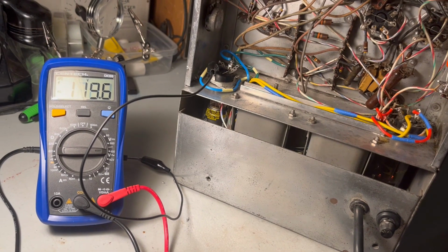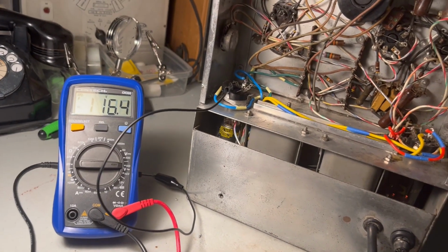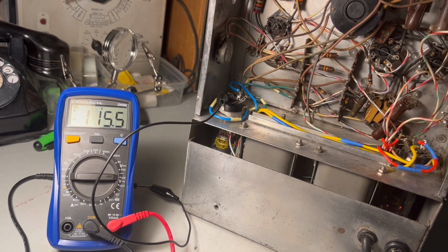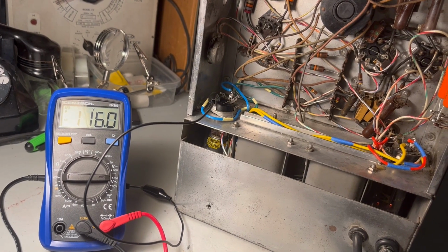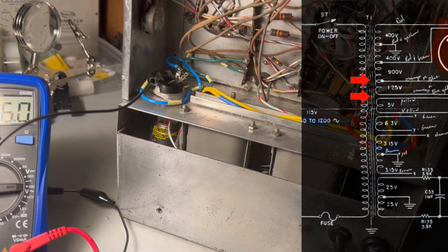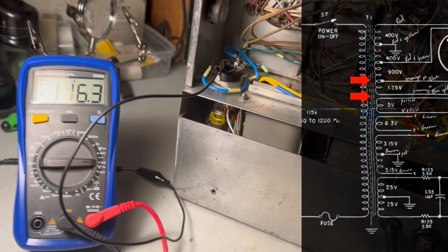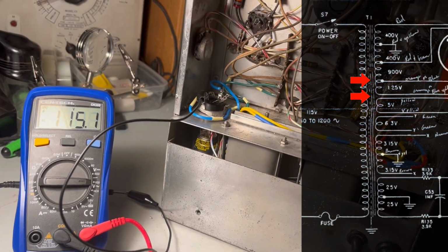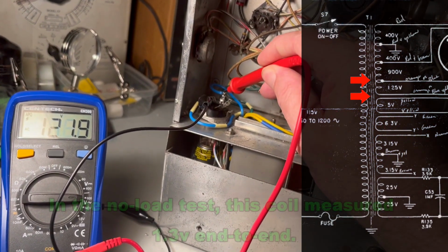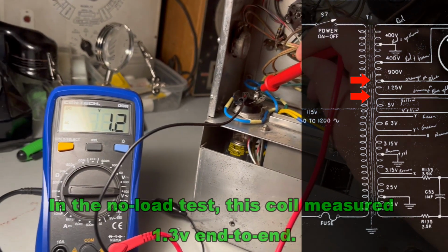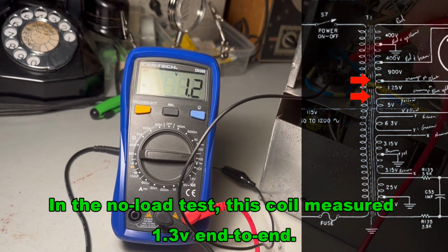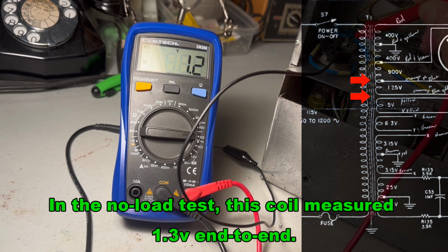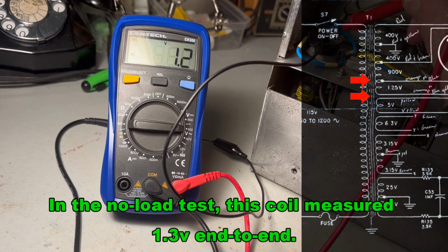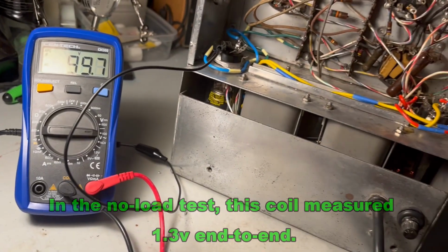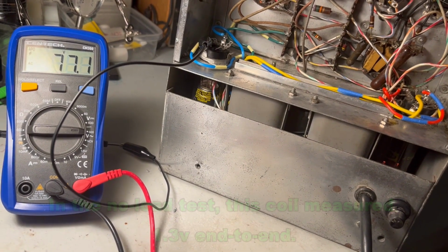Okay, I'm going to take a reading on the second half of the high voltage transformer. On this one I don't dare measure to ground, because to ground it's like 1300 volts. So instead I'm just going to read across and look at the potential of that coil - 1.2 volts is right about where we want to be. So that one looks pretty good.